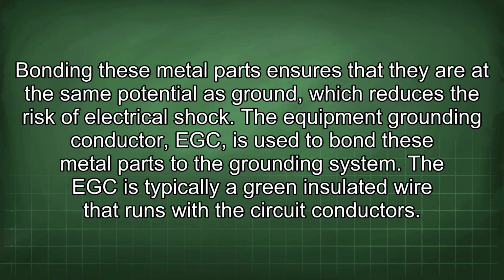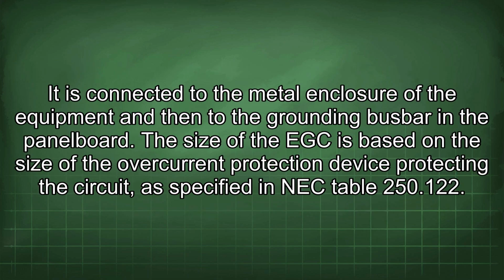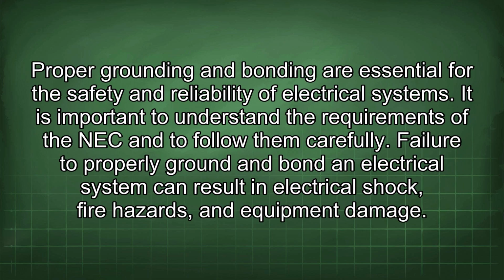The EGC is typically a green insulated wire that runs with the circuit conductors. It is connected to the metal enclosure of the equipment and then to the grounding busbar in the panel board. The size of the EGC is based on the size of the overcurrent protection device protecting the circuit, as specified in NEC Table 250.122. Proper grounding and bonding are essential for the safety and reliability of electrical systems.